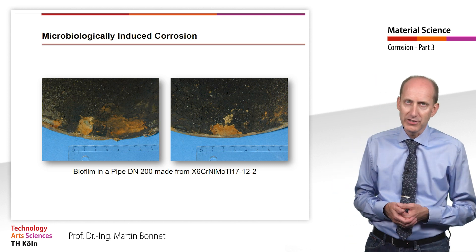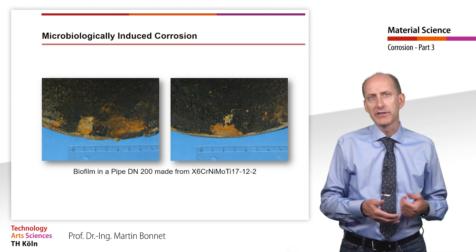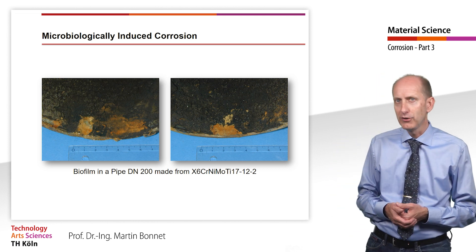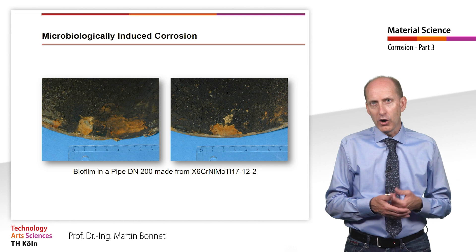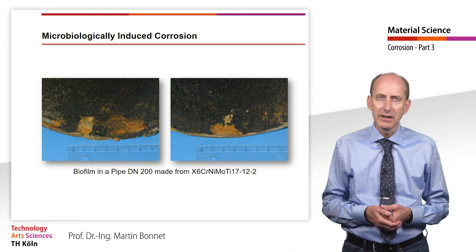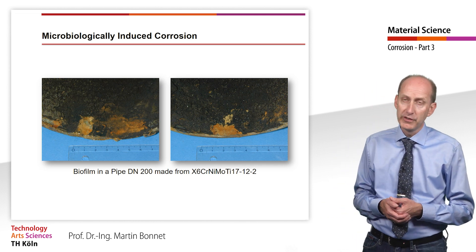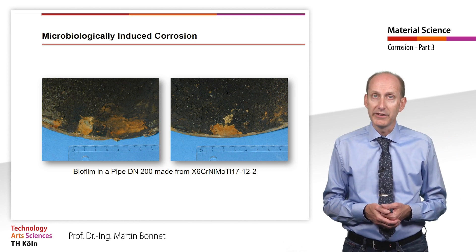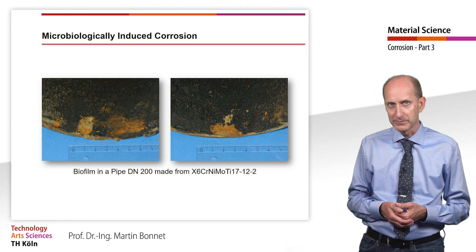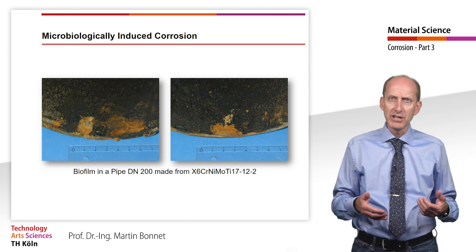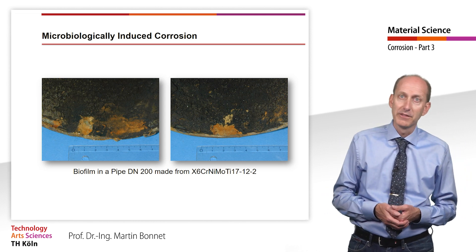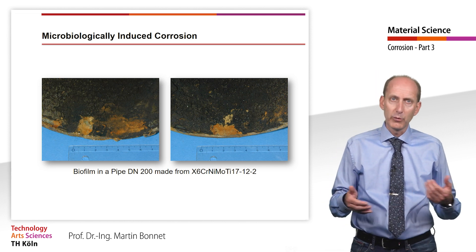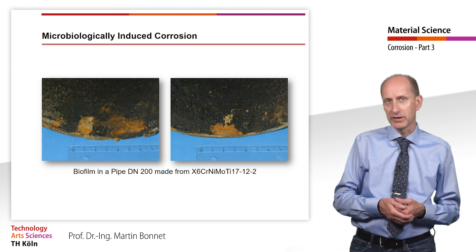What was actually tragic, however, was the coincidence of this aggressive biofilm with poorly executed welding work. In all welds made on site, clear tarnish was visible under the biofilm indicating that welding had been carried out without forming gas. It was the combination of these circumstances that caused the devastating total failure. All pipes were eventually replaced with polyethylene pipes. The costs amount to 125,000 Euro.